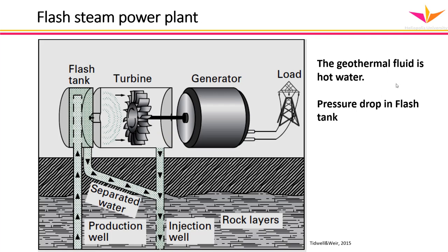Now we go to a bit less favorable conditions, so the enthalpy is a little bit lower, but still high enough to produce hot water. And that water is so hot that if you reduce the pressure, it will start to boil and you get steam in a system, so you have a flash tank, as they call it. The flash tank is, of course, not as efficient as having 100% steam, only part of your fluid becomes steam, so the efficiency is lower. But the pressure drop in the flash tank creates steam that can drive your turbine and your generator.